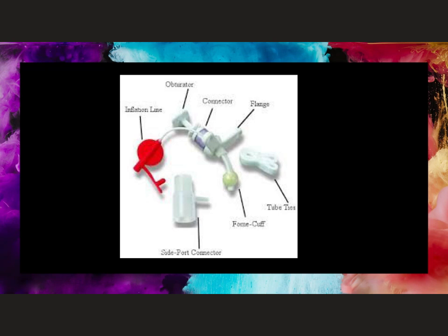It seals to the trachea by atmospheric pressure. So here you leave this little piece open, and it takes the pressure in the room and it will use that to seal the foam cuff here to the trachea. It's not common with patients until patients have tracheal damage, so long-term patients, because these trachs are very, very expensive.